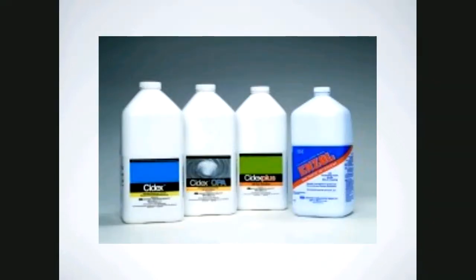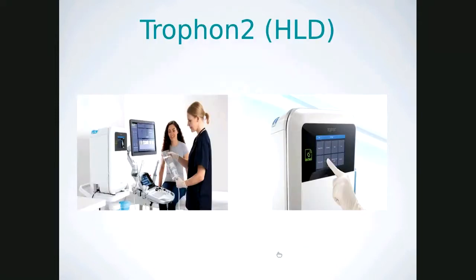The Trophon 2 — HLD stands for high-level disinfectant — uses a strong hydrogen peroxide solution. You place the transducer inside for a specified number of minutes; the process is fully electronic and prompts you on how to proceed. When you go through Week One on the PowerPoints, click on the Trophon 2 HLD link and it will bring you right to the website. It's a good idea to get the certification before you go out on your clinicals.